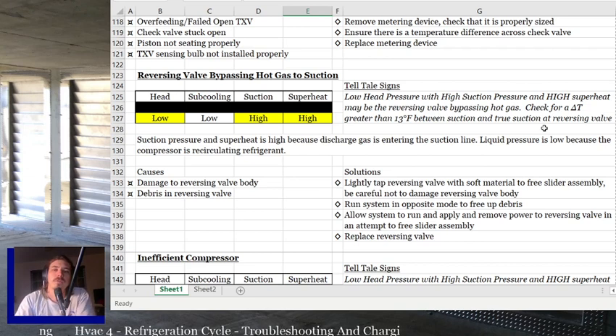And then if you let it run, power it in heating or power it in cooling, right? And then take the power off for a couple minutes and then switch it back to cooling. Try and get whatever debris is in there that's freezing up the assembly to move, and you might be able to get it working again. If that doesn't work, you gotta replace the reversing valve. Done.